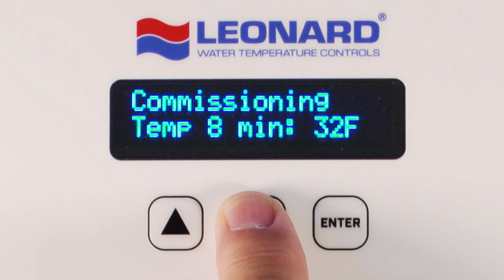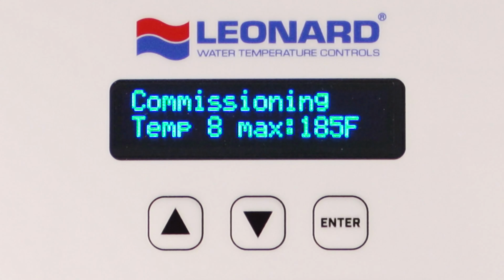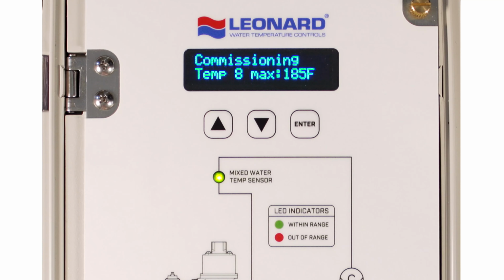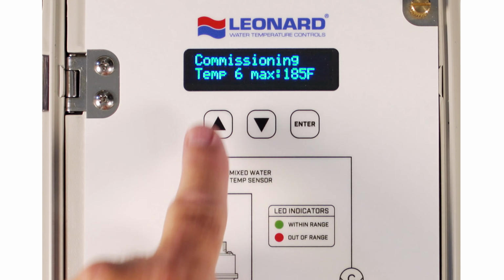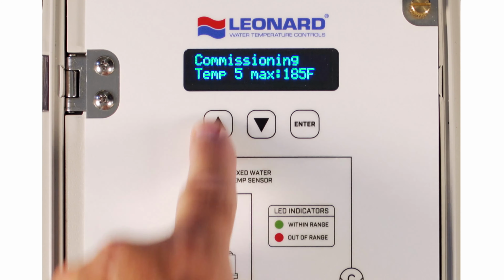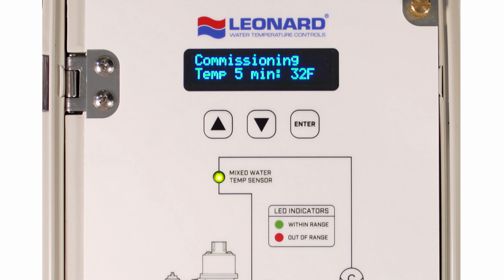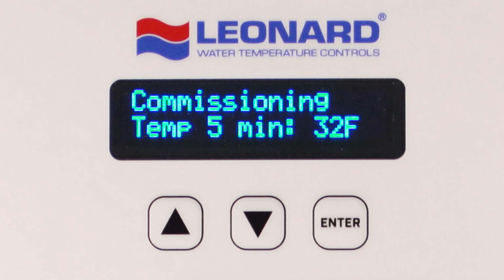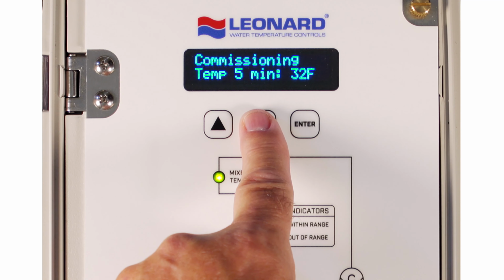Pressing down between 8 and 15 times displays commissioning temp min or max. This is the minimum or maximum temperature for RTD probes T5 through T8. Any temperature below this minimum temperature setting or above the maximum temperature settings will trigger an error message for that particular sensor. Default minimum setting is 32 degrees Fahrenheit. Default maximum setting is 185 degrees Fahrenheit.